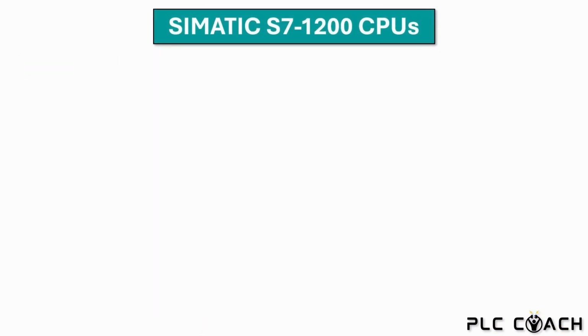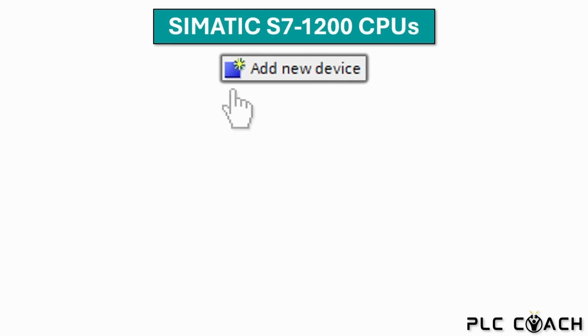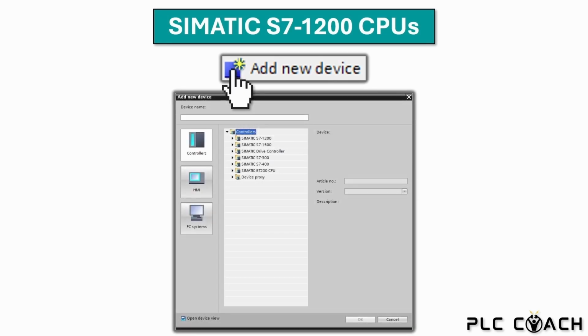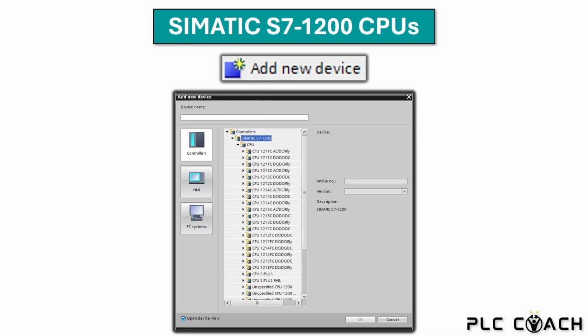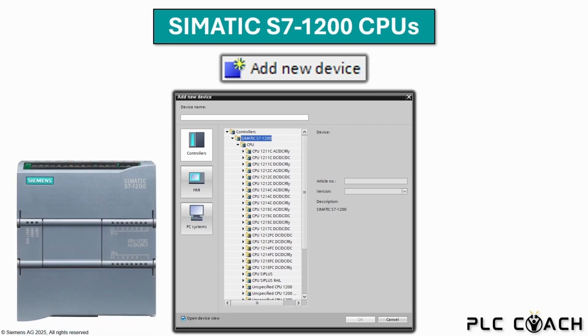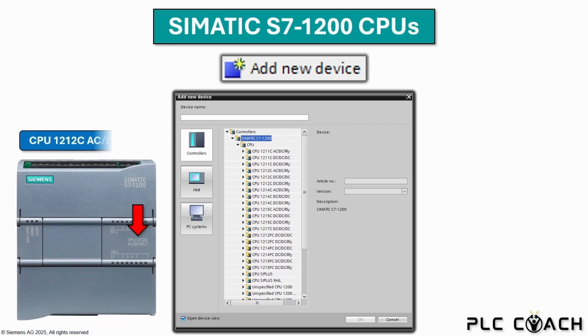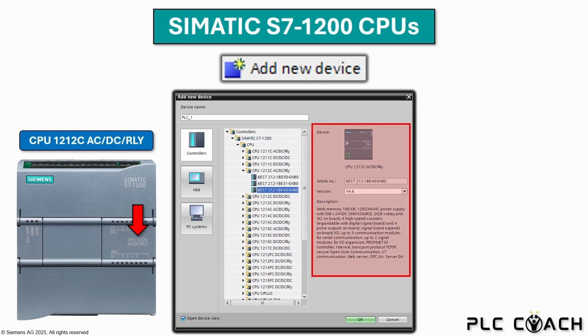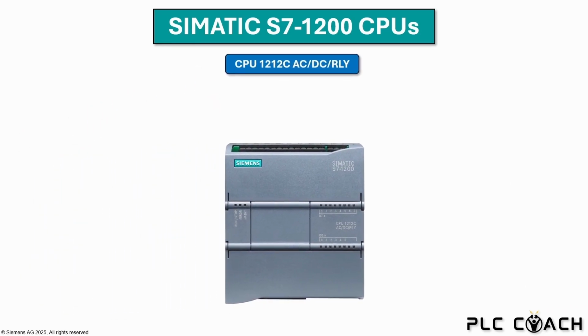When you add a new device in the TIA portal, you will see all the supported devices. The S7 1200 is suitable for small to medium-sized systems. There are slightly fewer devices compared to the Simatic S7 1500. Let's look at an example together. Here you can see the CPU 1212C AC/DC/relay. In the TIA portal you find a description of the device again. But the name of the controller also contains important information.